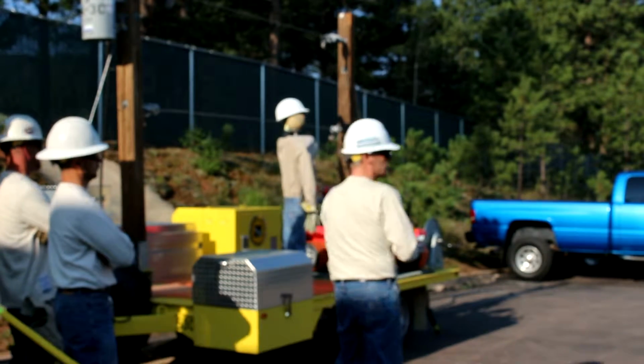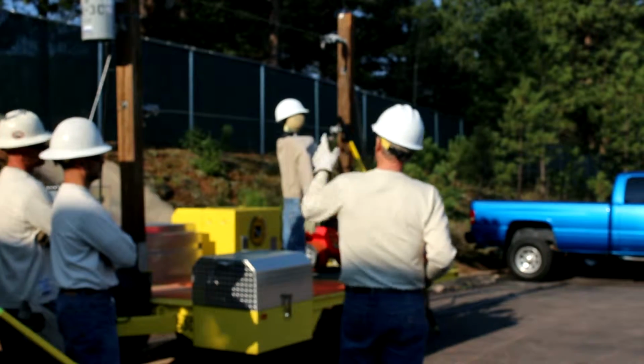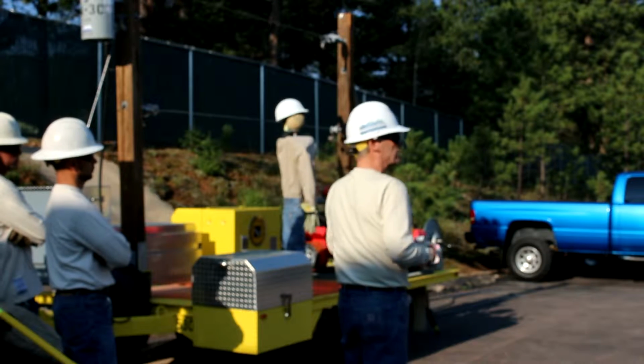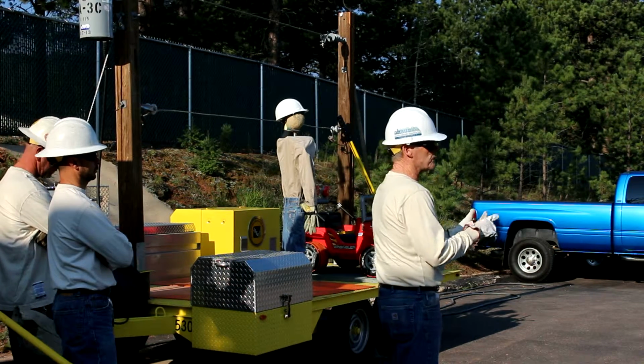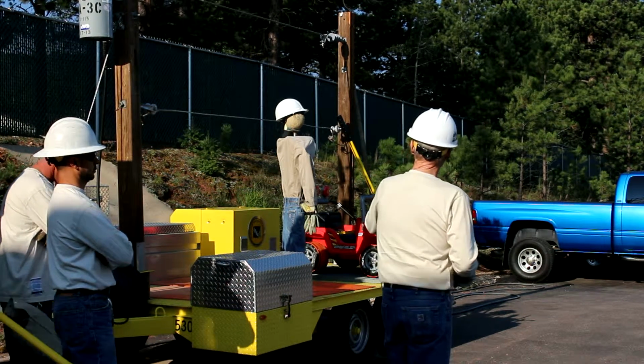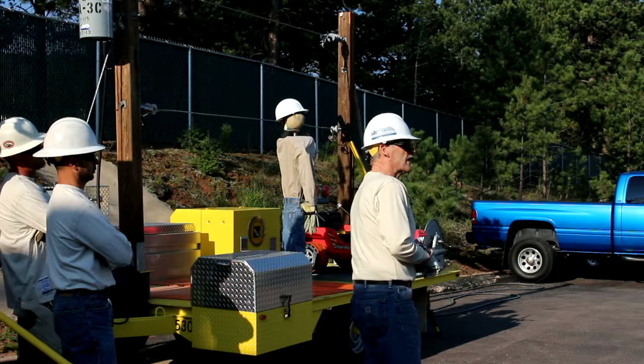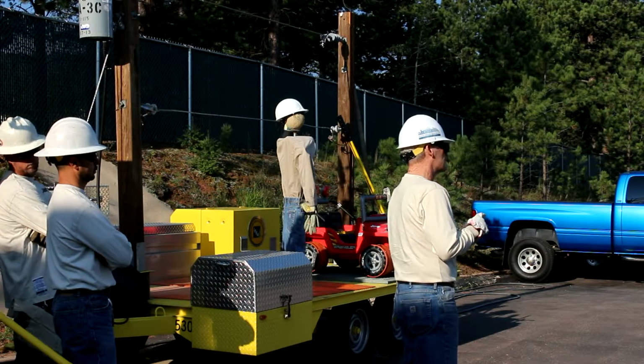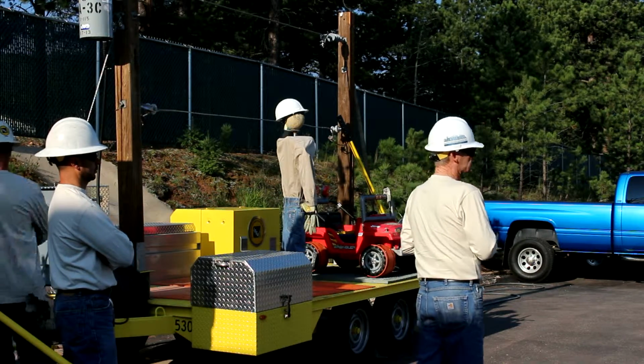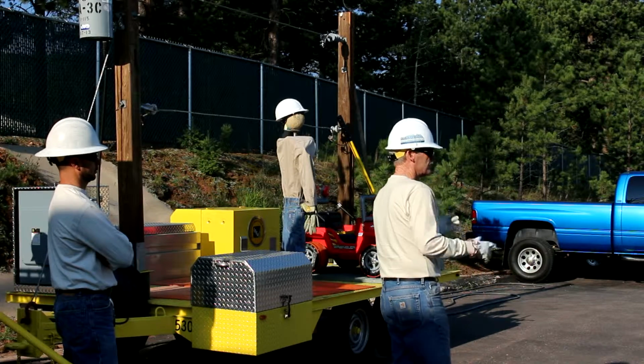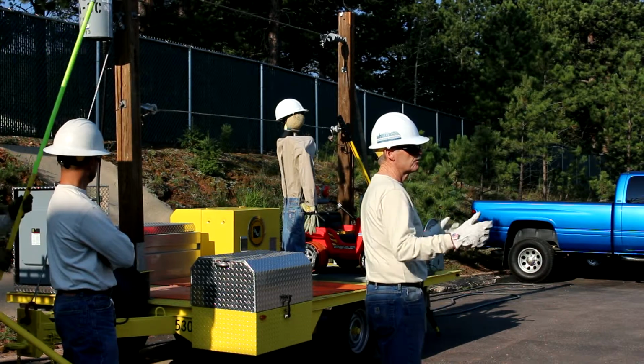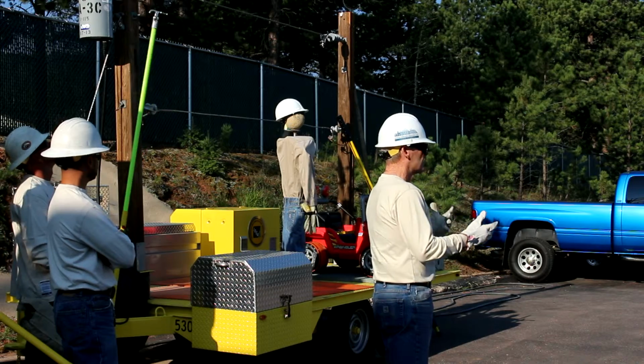We actually have a 3-point system to protect ourselves: a visible open, a manual open, and a guy watching. When we work on lines, if it's hot, we always have 2 guys watching. We work everything with sticks that are dielectrically tested to withstand voltage for 100,000 volts per inch. We're working with 8 foot sticks, so we're good. It doesn't break down.